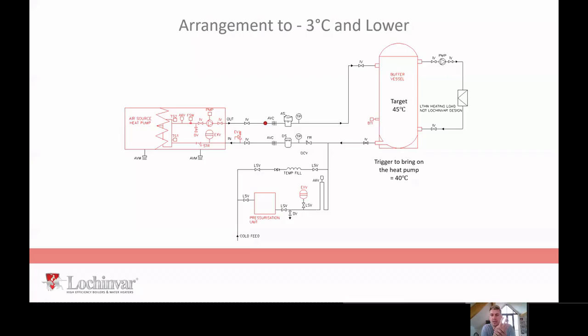4 times the flow rate means a massive increase in your velocity, and the impact of that is you're going to want to be increasing your pipe work sizing. So just bear that in mind as well. 5-degree delta T means much higher flow rate. Much higher flow rate means bigger bore pipe work, because otherwise your velocity is going to get too high. It's going to scrub the inside of the copper pipes out, leads to premature failures.